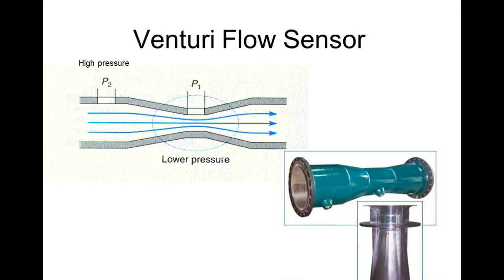So controlling the pressure and controlling the flow rate are two different things. If this is feeding an actuator and we control the flow rate, what do we control on the actuator? We control the speed of the actuator. And if we control the pressure, then what do we control? The force, not the flow, the force. So the flow rate determines how fast the actuator moves, and the pressure determines how much force the actuator can generate.